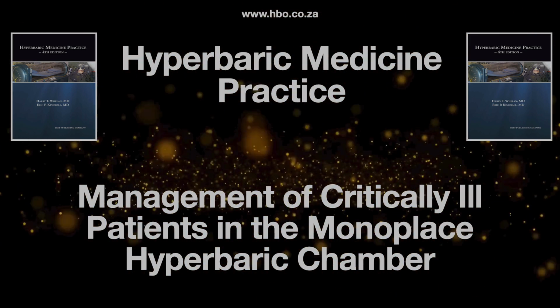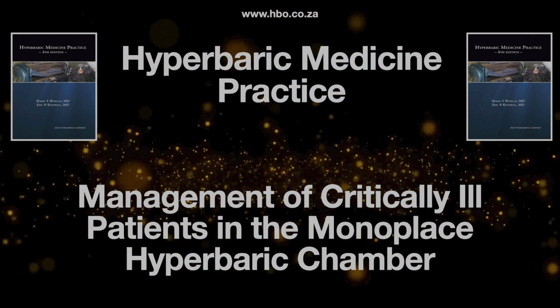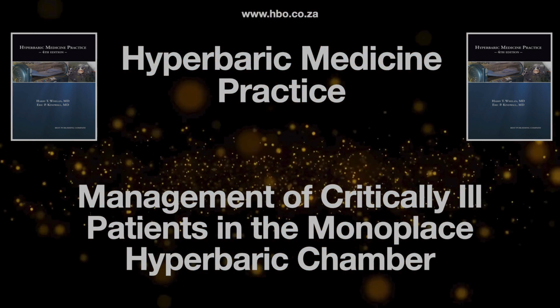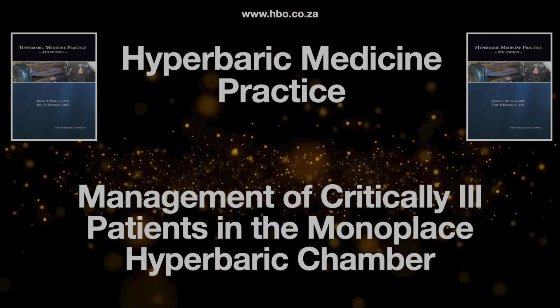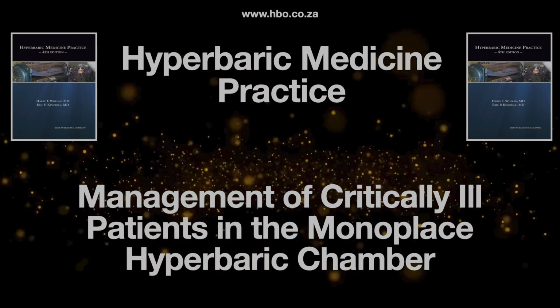Absolutely. Okay, let's touch on defibrillation. Seems risky in a high oxygen environment. What's the thinking there? It's a valid worry. Spark plus high oxygen equals potential fire. So some people recommend moving the patient away from the chamber right after they come out before shocking them.